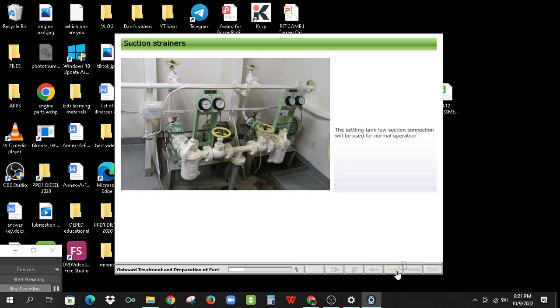The settling tank low suction connection will be used for normal operation. If there is a build-up of dirt in the bottom of the tank, or if vessel movement in rough weather is likely to disturb the settled dirt and water, then the high suction can be used. This will reduce the amount of dirt and water drawn from the tank by the pump.